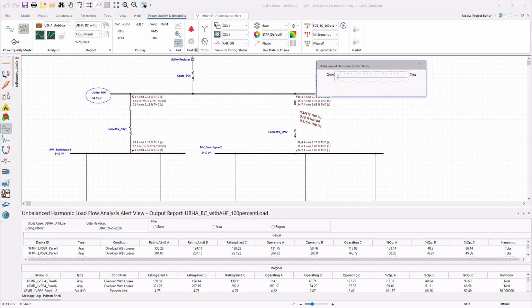And additional characteristics of this technology, such as power factor correction, phase load balancing, and dynamic harmonic mitigation adjustment, match with the operating requirements for the client systems were also recommended. And based on the common findings for all the sites, it was recommended that for future sites, K-rated transformers are installed for the panel. So as observed generally for all the sites in the study, further loading could create unbalanced conditions and introduced additional harmonic distortion to the system. So having these K-rated transformers and having these filtering devices in place could take care of harmonic distortions due to unbalance created with the additional loading in the system in future.